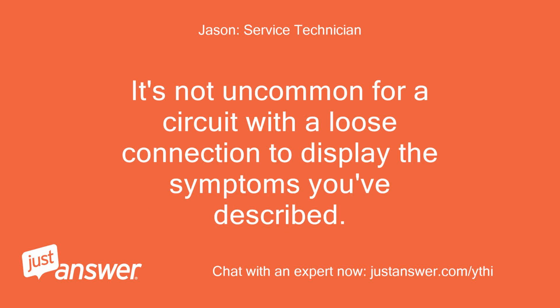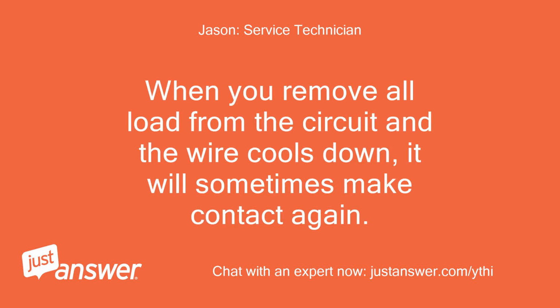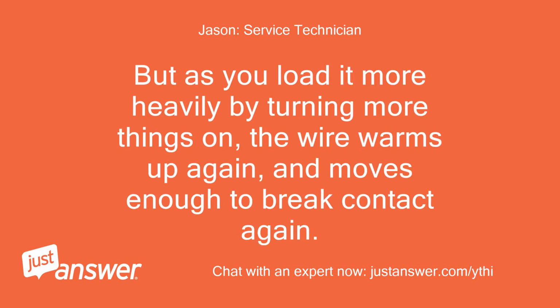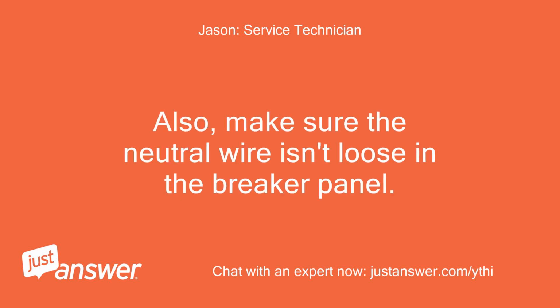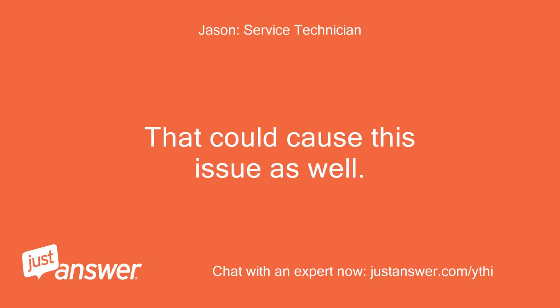It's not uncommon for a circuit with a loose connection to display the symptoms you've described. When you remove all load from the circuit and the wire cools down, it will sometimes make contact again. But as you load it more heavily by turning more things on, the wire warms up again, and moves enough to break contact again. Also, make sure the neutral wire isn't loose in the breaker panel. That could cause this issue as well.